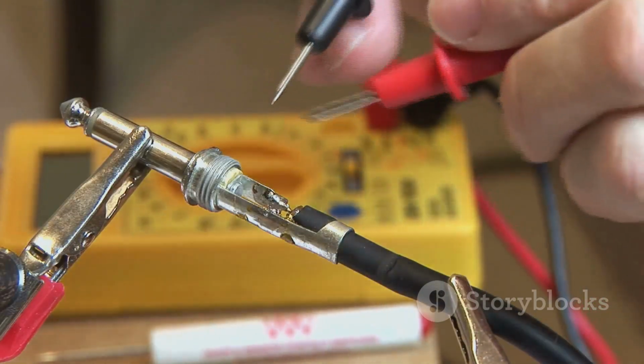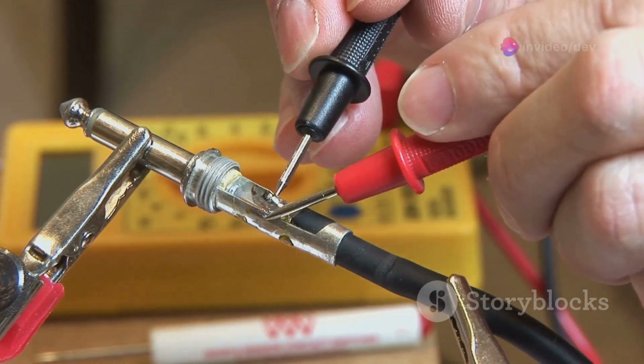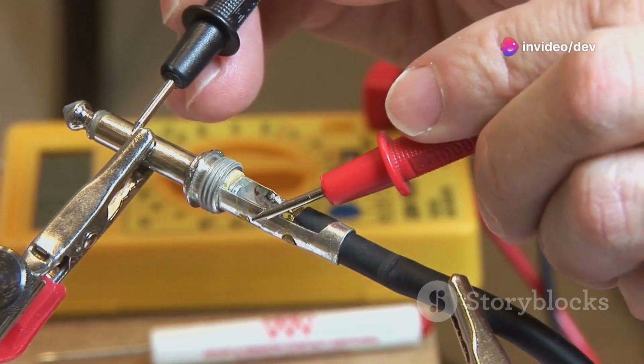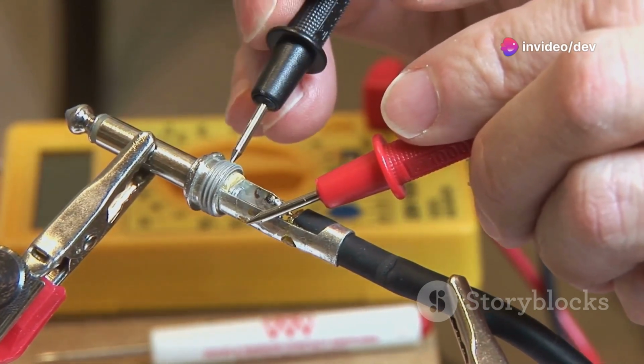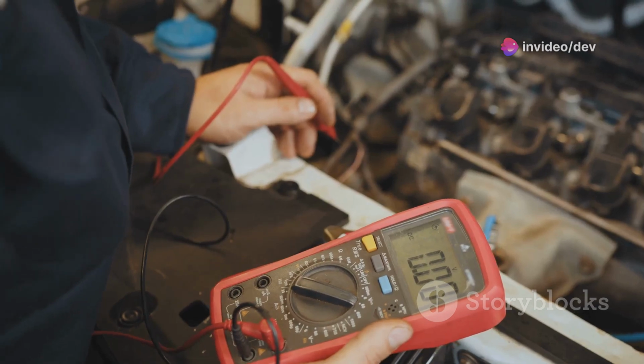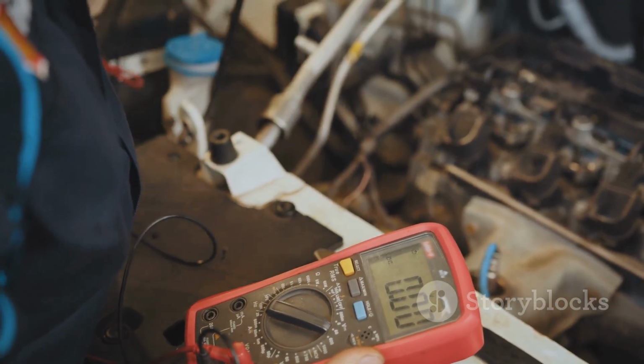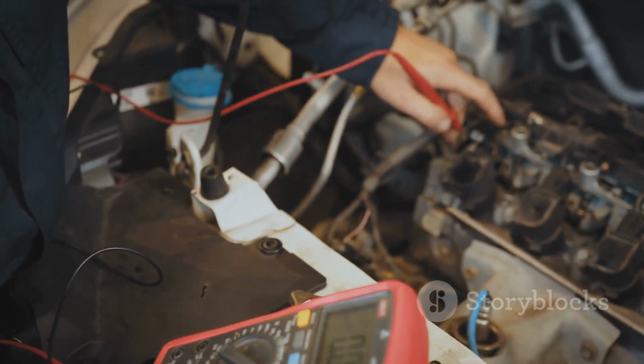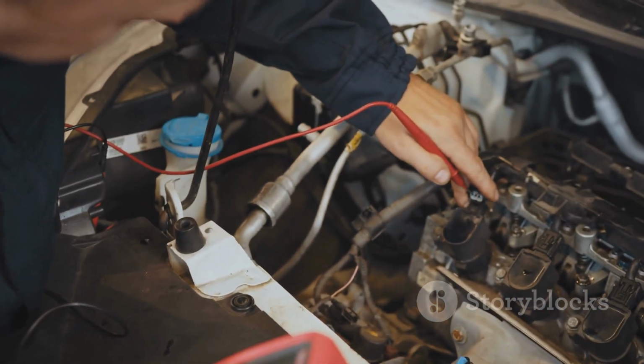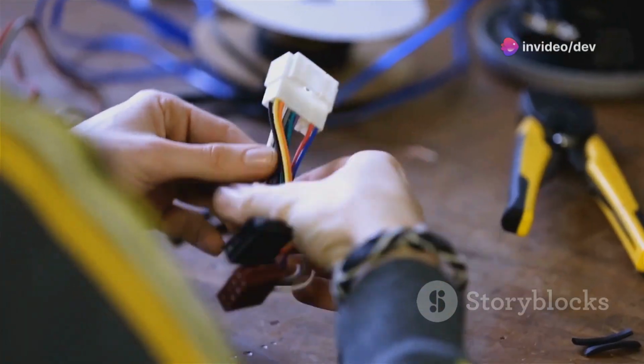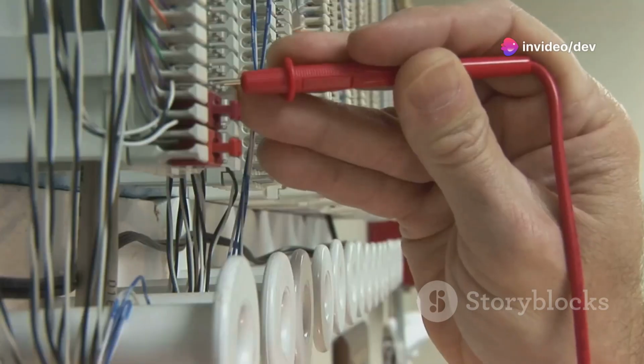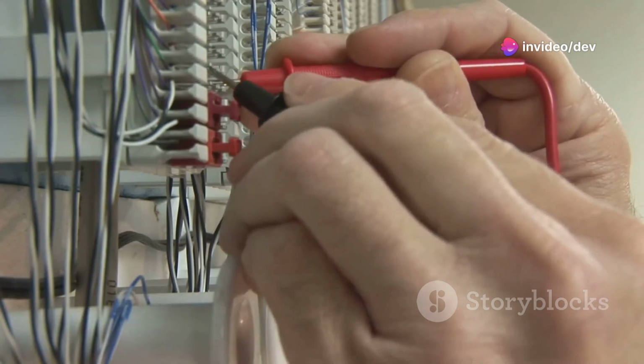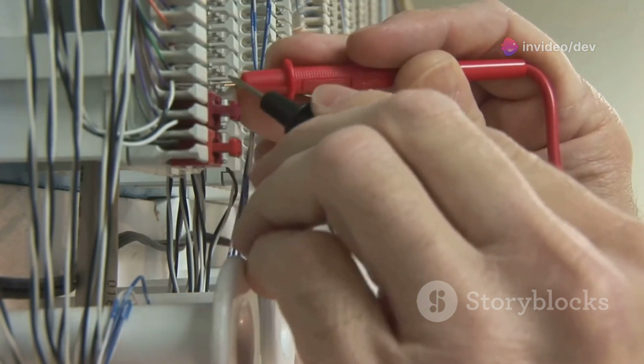Set the multimeter to the appropriate setting and touch the probes to the compressor's electrical terminals. Make sure you have a firm connection to get an accurate reading. If the multimeter beeps or shows a reading, it indicates continuity. This means that the electrical circuit is complete and functioning as it should. If not, there might be a wiring problem. Faulty wiring can lead to serious issues, so it's important to address this immediately.